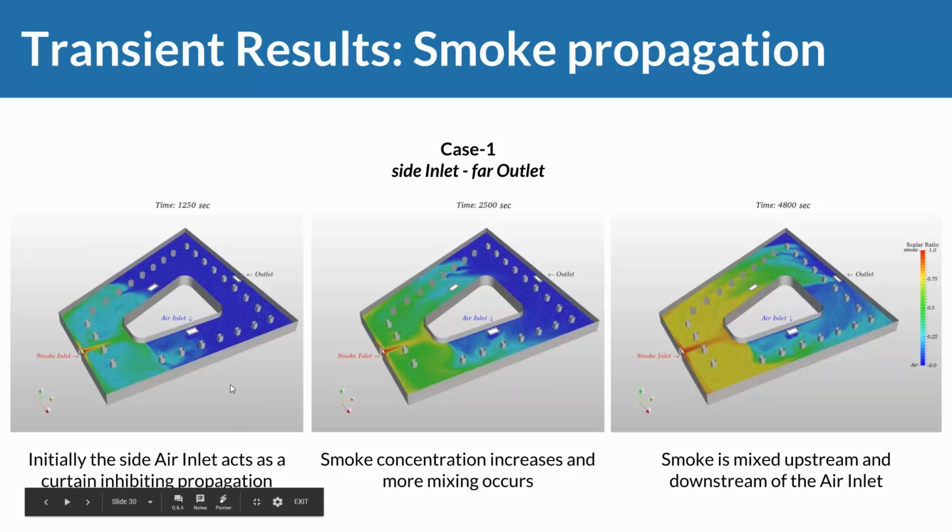It's oftentimes also used to keep warm from cold air separated. It effectively serves as a curtain, and the smoke does not pass that part. On the left, it simply propagates through. Let me bring in the pointer.